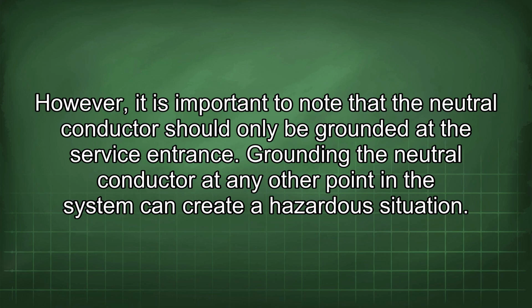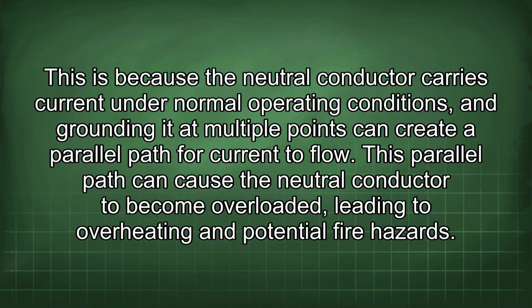However, it is important to note that the neutral conductor should only be grounded at the service entrance. Grounding the neutral conductor at any other point in the system can create a hazardous situation. This is because the neutral conductor carries current under normal operating conditions, and grounding it at multiple points can create a parallel path for current to flow. This parallel path can cause the neutral conductor to become overloaded, leading to overheating and potential fire hazards.